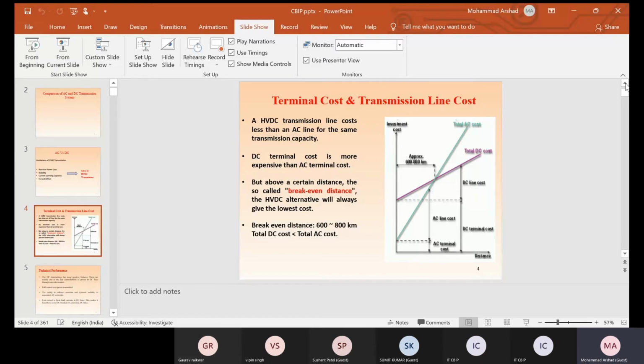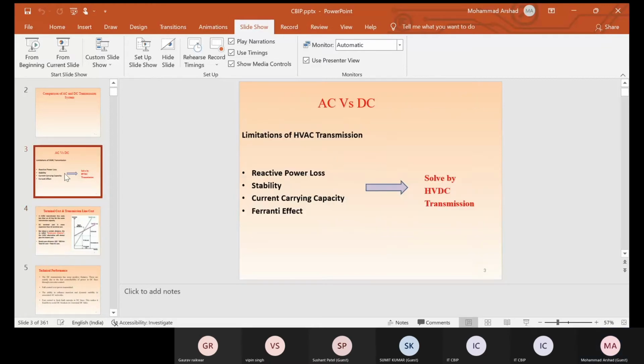So we would like to keep it less than 50%, meaning delta should be 30 degrees or less. Our transient stability margin should be there, so that in case of a fault or any situation, your system may remain stable.